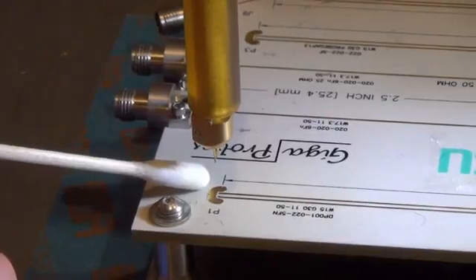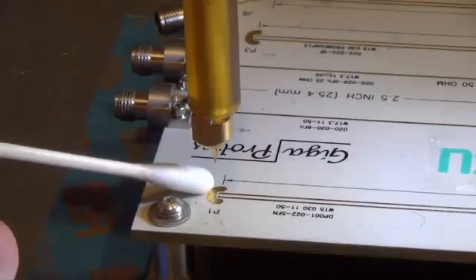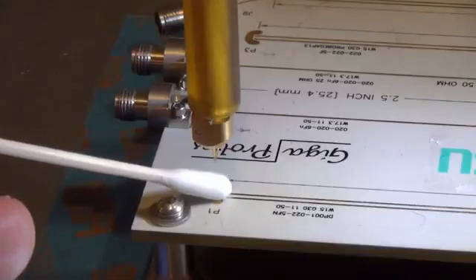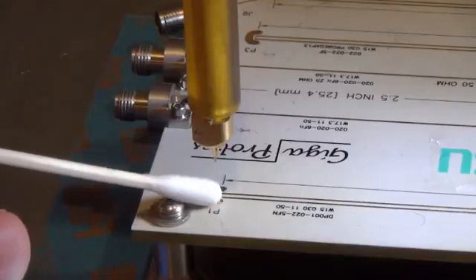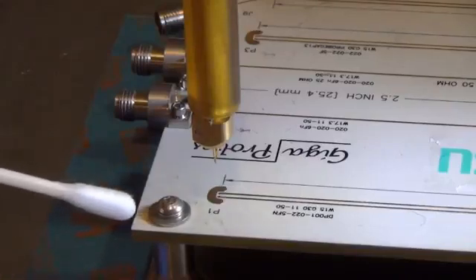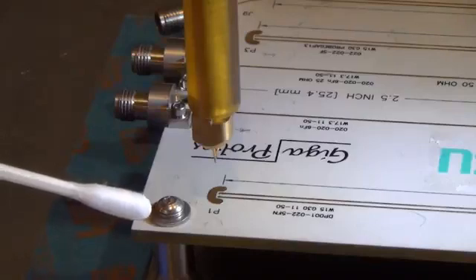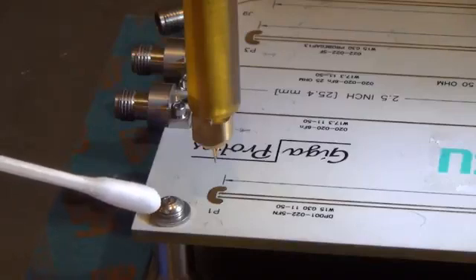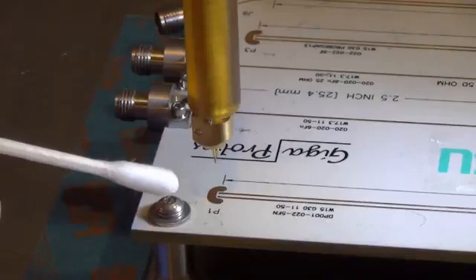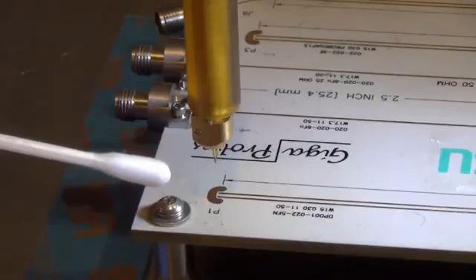Now with the probe raised over the test pads, before you probe, take some alcohol on a swab and swab the test pads to get off any oxide. Also check for resin. A lot of prototypes have resin still on them, which is very difficult and impossible to probe through. This will assure an excellent measurement.